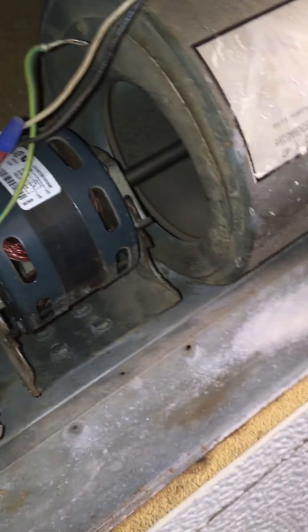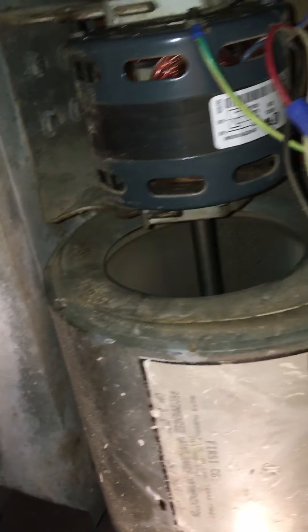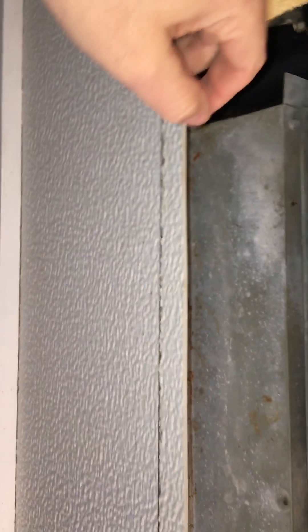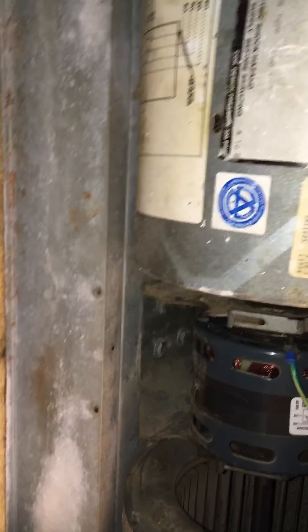When you want to take this motor off, all you have to do is undo the white wire and the black wire. Obviously, turn the system off first. You're going to turn the motor off so it's not blowing anymore, then undo the black wire and the white wire — that's the only wiring to the motor. Then on almost all of them there are two wing nuts on the bottom; you loosen those wing nuts and you can just lower this part down. The coil stays up there, but the motor and blower system comes out.